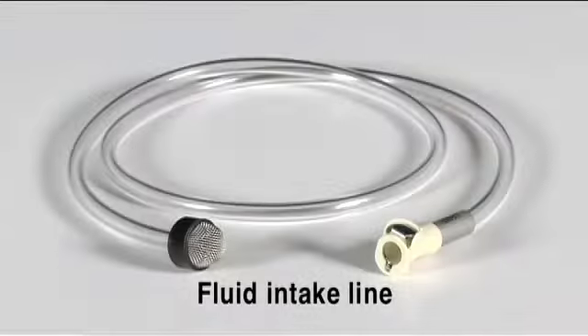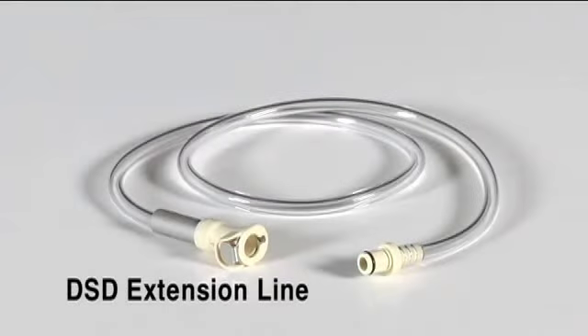Fluid intake line. This tubing snaps into the in port on the Scope Buddy unit and allows fluid to be drawn up from the sink or container into the Scope Buddy. DSD extension line. This extension line is used by facilities with Medivators DSD reprocessors. The DSD extension line snaps into the out port on the Scope Buddy unit and allows connection to a Medivators DSD hookup, which attaches to the endoscope. Fluid will be delivered through this tubing to the DSD hookup.